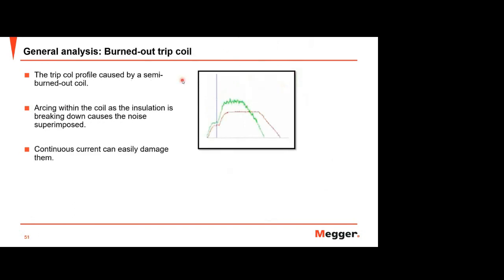And this one, burned out trip coil. So if you see something similar to this, this is a semi burned out coil, not totally burned. Because the operation of the coil is very short, in milliseconds, in some cases the breaker still operates, maybe with some limited change like this one, due to the higher current needed to force the latching part. So you can see the mechanical part also getting hard to work. So this increases the pick up level on the second peak. So if you see this one, this means a semi burned out coil. So sometimes, if you're lucky, the breaker still operates, but be careful: if you inject voltage for a little bit longer time, the coil will break. And if the coil breaks, of course, it is damaged. You cannot operate the breaker anymore.